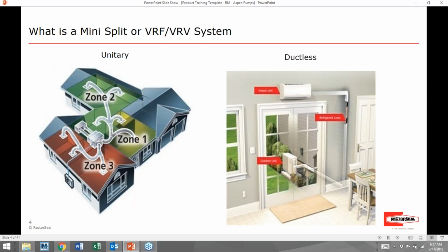So continuing on, what exactly is a mini split and how does it differ from a unitary system? Looking at the picture on the left, you can see there's still an outdoor unit and there is an indoor unit, but the indoor unit is connected to each space or zone by ductwork. The picture on the right explains what a ductless system is. You still have an indoor unit here and an outdoor unit there, but they are connected by line sets, control wire, and condensate management. The difference is you will have an indoor unit like a high wall or a ceiling cassette in each of the spaces that you're trying to heat or cool.